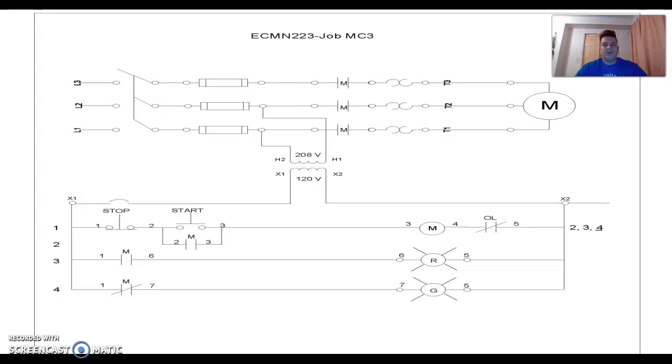The first thing I want to get to is three-wire control circuits in general, and how you should try to create a paragraph, or at least a couple of good sentences, explaining how the control circuit is going to operate. Basically, a sequence of operations. You could do it one of two ways. You could either come up with your own schematic and write the sequence of operation based on that, or you can try and write a sequence of operation and then design the control circuit, whichever way you want to do it.